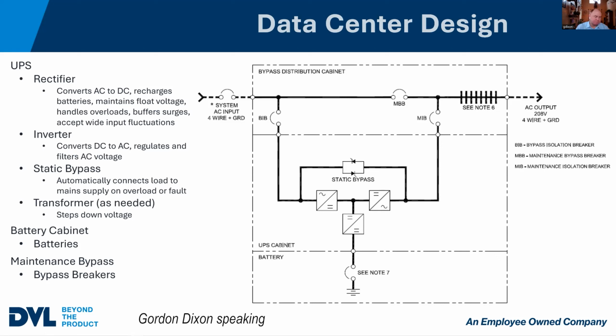The last primary piece of the internal piece of a UPS is going to be a transformer. Now, this is only if it's needed. Sometimes, on the previous drawing, I showed the one line, you'll see that the UPS might be feeding a panel and the panel itself is feeding equipment downstream from that, right? So if you're going to go from a 480 volt utility power into the UPS and you have a 480 volt output and it feeds a transformer downstream, you don't need a transformer inside of the UPS.